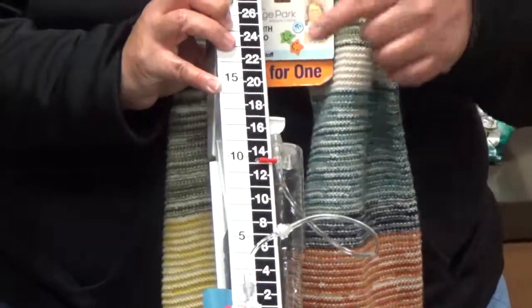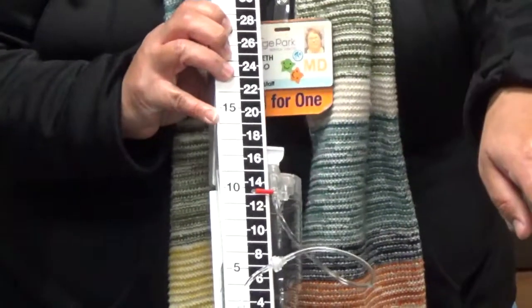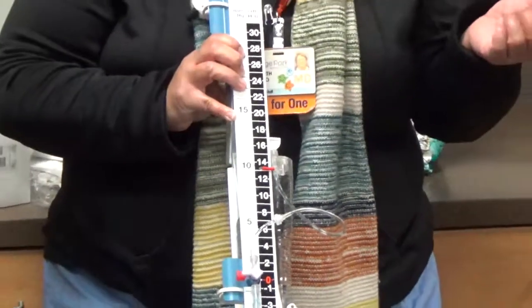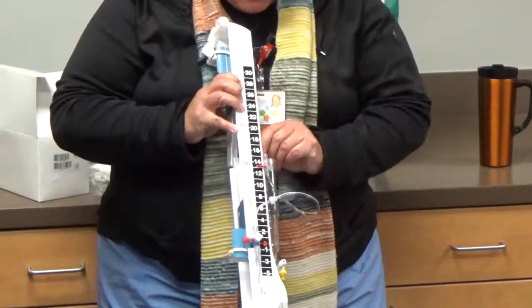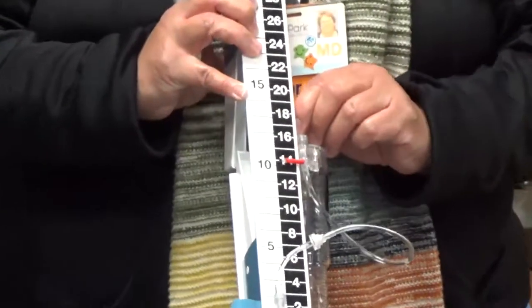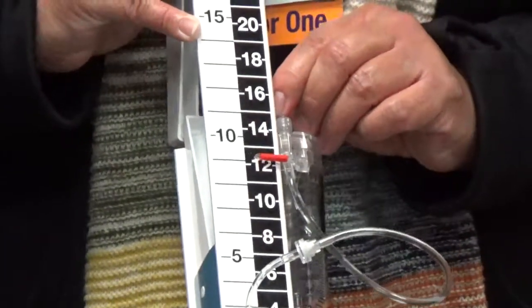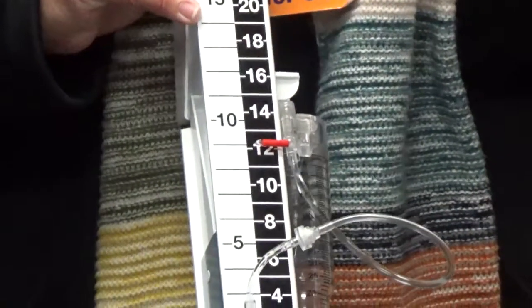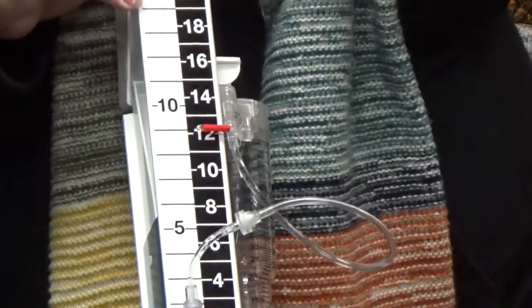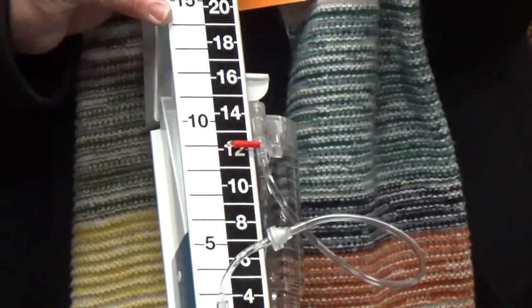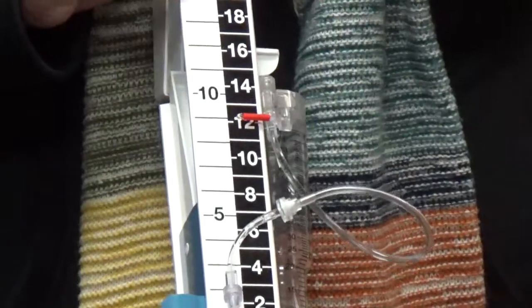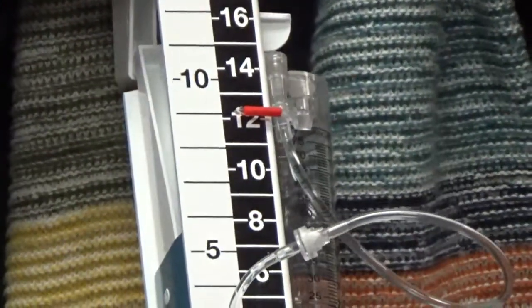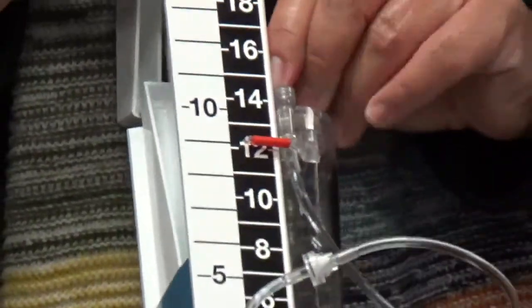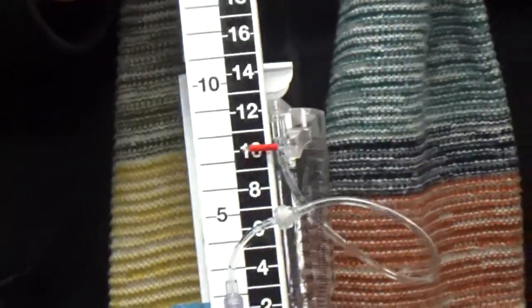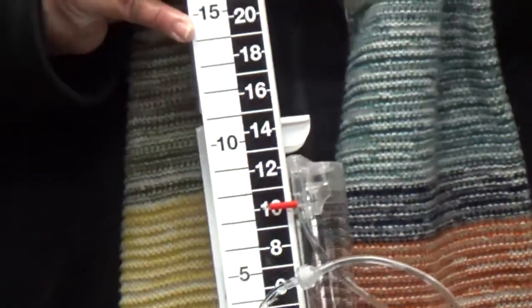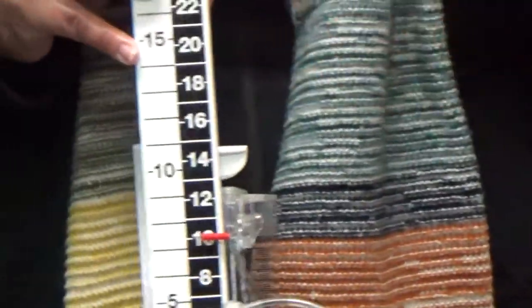Now I know this pressure has to be higher than the CSF, the ICP, or else it wouldn't backflow, right? So then I'll drop it back down. Say the backflow started at 14, okay? Then I'll start to drop it again, and say I get to 12. It's usually when you get to the manual ICP, the true ICP, that it won't go forward or backwards. You'll just start to see the pulsations at the top of the meniscus, okay? That's your ICP. And then when you're done with that, you put it back to 10, where I had it as the resistance, because that's going to allow a small amount of continuous flow.